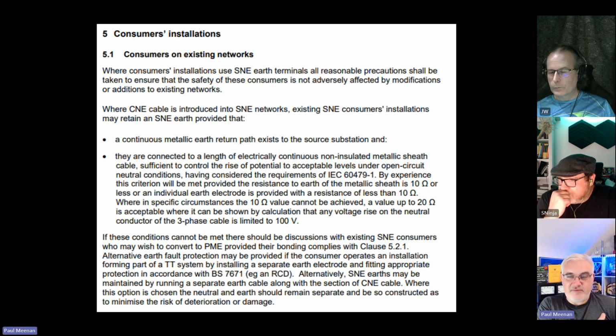Okay, well, you're repairing it with a PME, so you're kind of making it worse. But anyway, the next bullet point is they are connected to a length of electrically continuous, non-insulated metallic sheath cable sufficient to control the rise of potential to acceptable levels under open circuit neutral conditions. Having considered the requirements of IEC 60479-1, by experience, this criteria will be met, provided the resistance of the earth of the sheath is 10 ohms or less, or an individual earth electrode is provided with a resistance of less than 10 ohms.